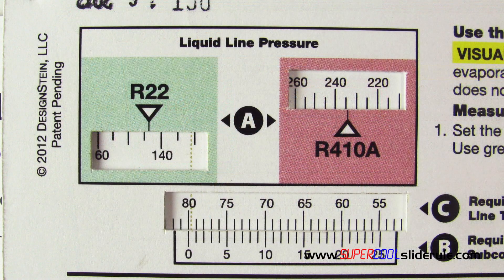To use this, we set the temperature to 80 as shown here directly over the zero. In the R22 window, we will note that the pressure is 144. And in the R410A window, we note the pressure is 235.